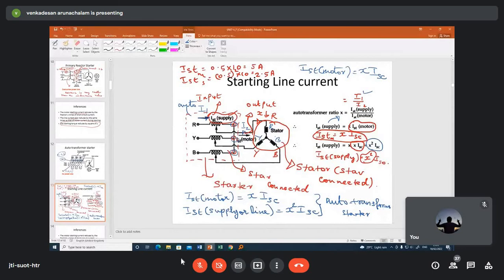So when we use an auto transformer starter, the motor starting current is reduced by X times, but the supply or line current is reduced by X squared times. That is the biggest advantage. The motor acts as a load to the supply line. The motor starting current reduces by X times, but the current drawn from the supply reduces by X squared. It means you are not loading the supply line much with your motor. That is another advantage of the auto transformer starter.